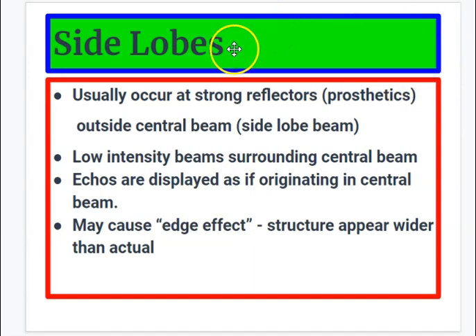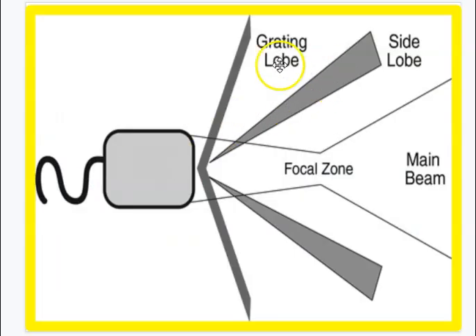We also have something called side lobe artifacts. These usually occur at strong reflectors outside the central beam, which is the side lobe. Low intensity beams surrounding the central beam is what side lobes are. The echoes are displayed as if originating in the central beam and may cause some sort of edge artifact, so the structure may appear wider than actual due to these side lobe artifacts. And if you look at the transducer here, you can see we have a focal zone. This is where our beam is going, our main beam. This is where we see things the best.